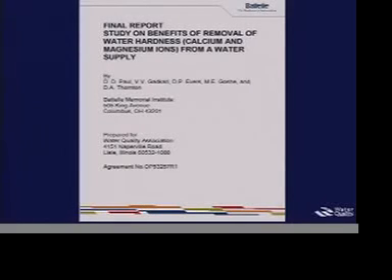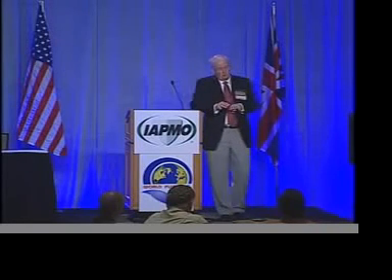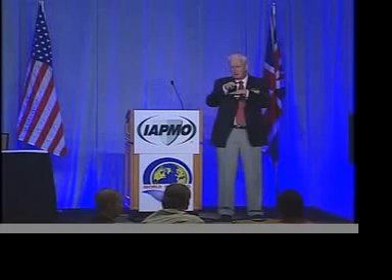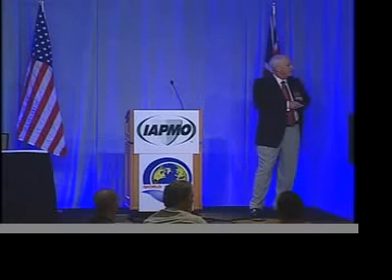When you download the report, you'll find summary table ES-1 showing efficiencies for instantaneous, gas storage, and electric storage heaters at the beginning of the test and how efficiency dropped on unsoftened water — softened water maintained efficiencies while hard water did not. With the electric water heaters, we did not see a drop in efficiency during the test because the heating elements are positioned up off the bottom of the tank, allowing scale to slough off. The heating elements appear to be made of a material that scale doesn't stick to well, so scale sloughs off to the bottom. However, we did accumulate about twice as much scale in the electric heater tanks on the hard water side compared to the gas heaters.